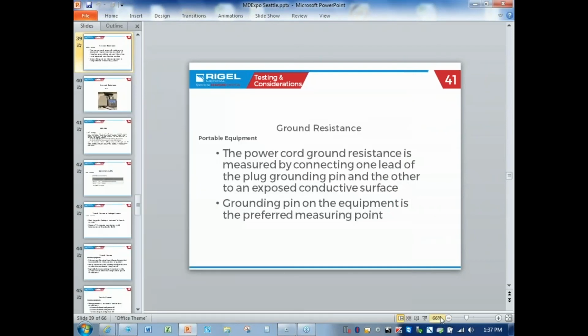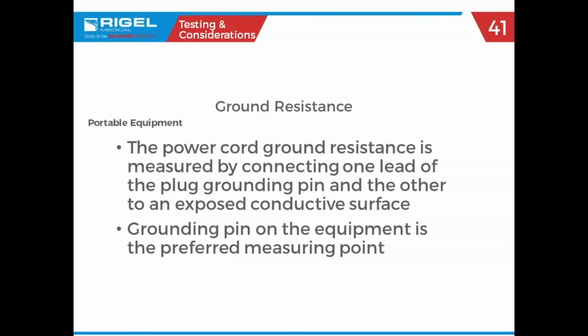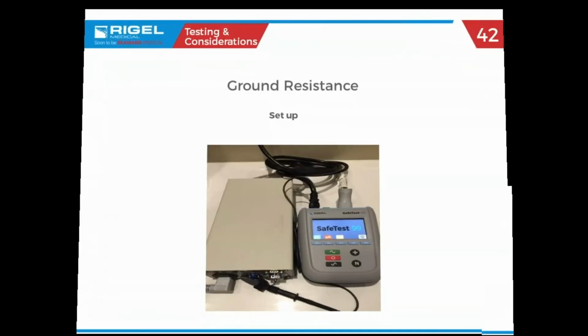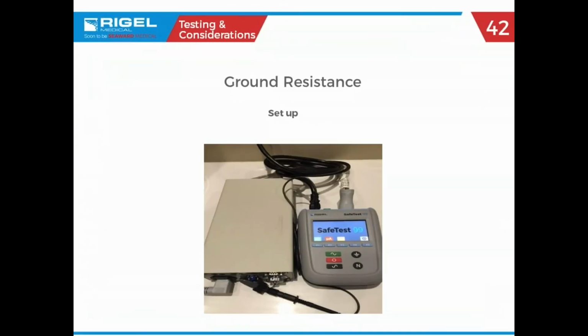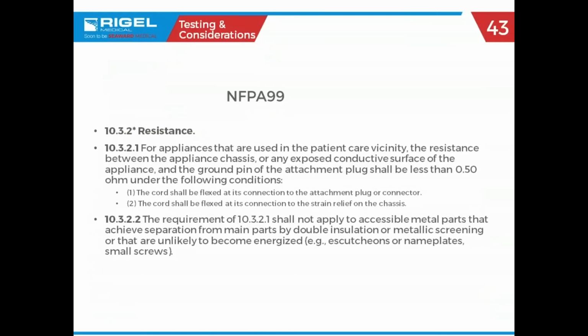In my presentation, I'm thinking it's the next slide. We talk about what the limits are. What does good look like? Oh, look at that. So we're looking at ground bond resistance here. 0.5 ohms. So anything below half an ohm, according to the NFPA 99 standard, is acceptable. Manufacturer's spec, 60601, says 0.3 ohms. Why the difference? Any ideas? Any thoughts? Yeah. Time, oxidation. Exactly. So the manufacturing standard, 60601, everything's nice, fresh, and clean.